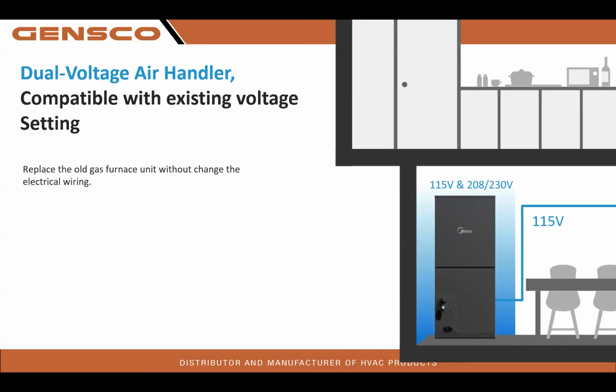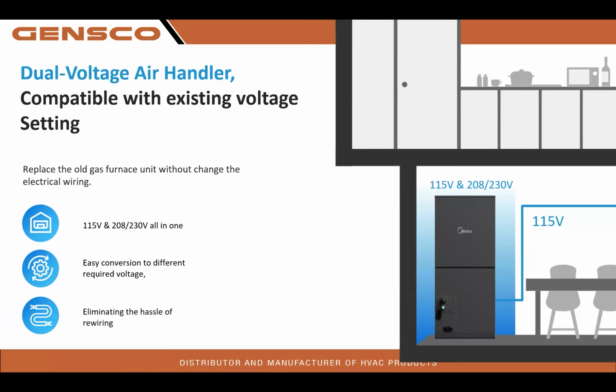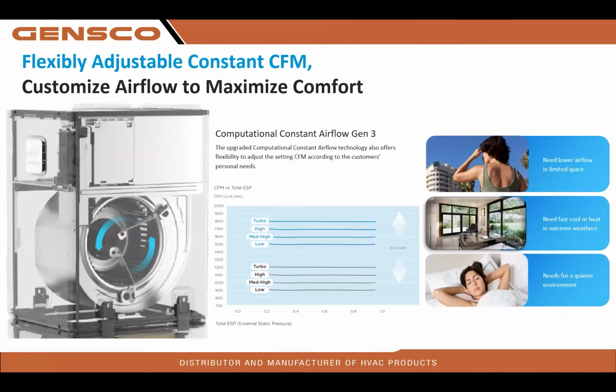115 to 208, 230 volt, you get a pick. It's an all-in-one package. Easy conversion to different required voltages, eliminating the hassle of rewiring. Like I said, the only time you need to land 208, 230 is if you're using strip heat. Flexible, adjustable, constant CFM. Customize airflow to maximize comfort. You have the ability to go low, medium, high, or turbo right from the TL04 stat.